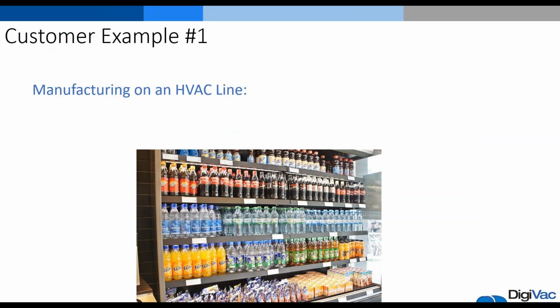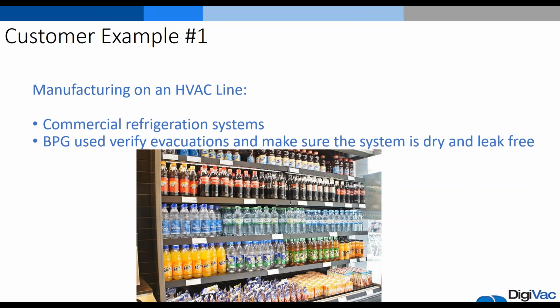To go into a few customer examples of the gauge, there's manufacturing on an HVAC line, which means that you can use the Bullseye Precision Gauge to monitor commercial refrigeration systems and make sure everything is dry and leak-free. You would do this by plumbing the gauge itself into the vacuum system and seeing if it maintains pressure.